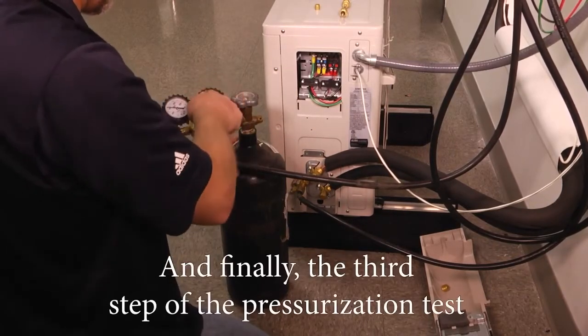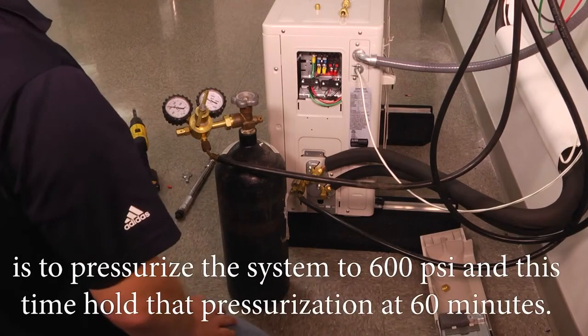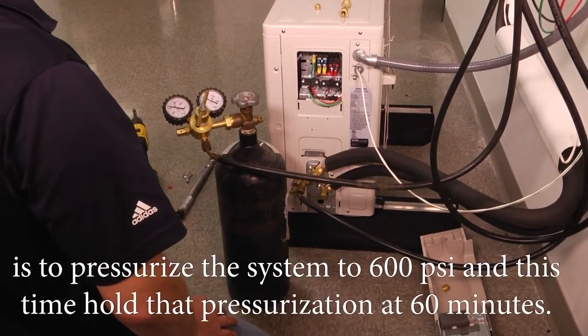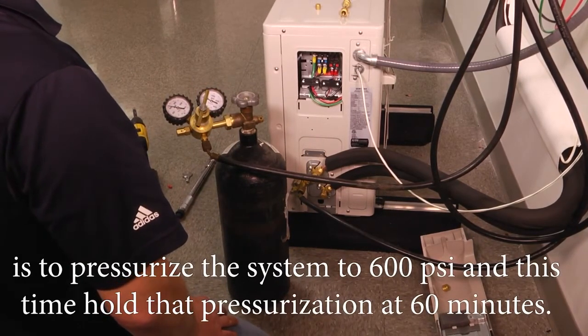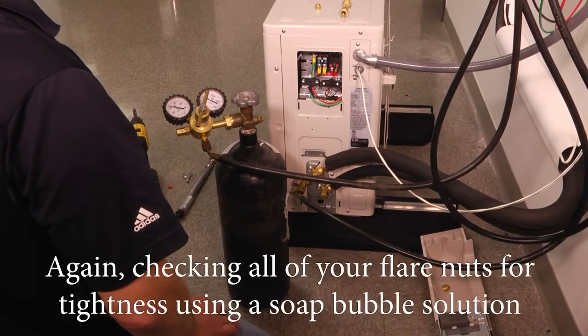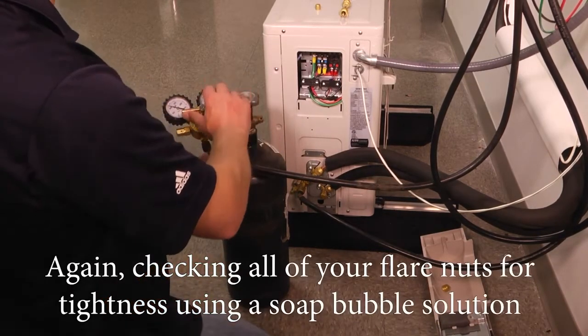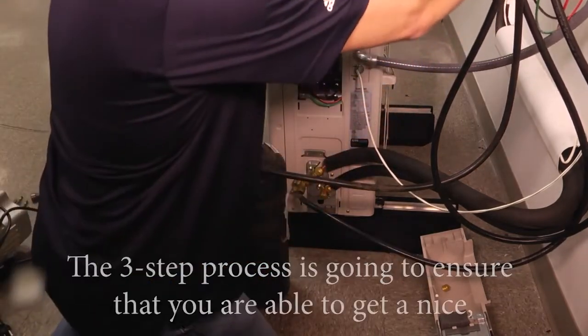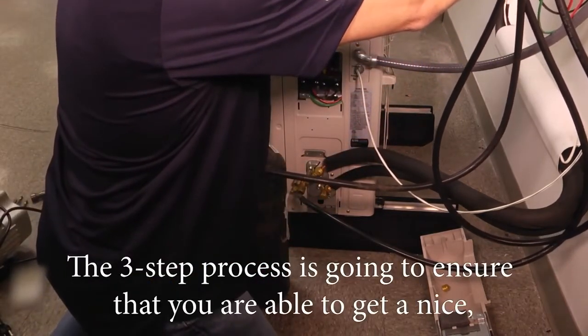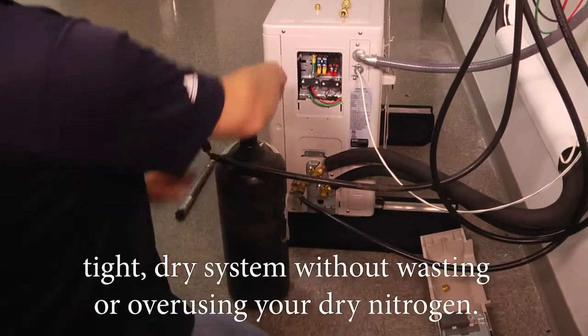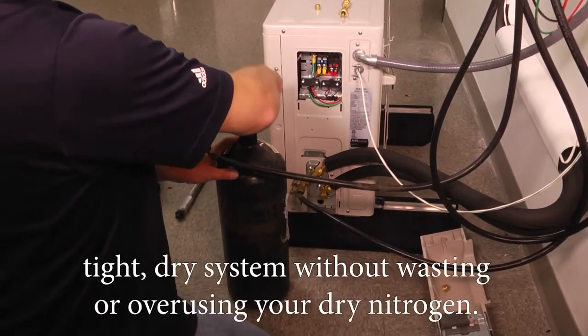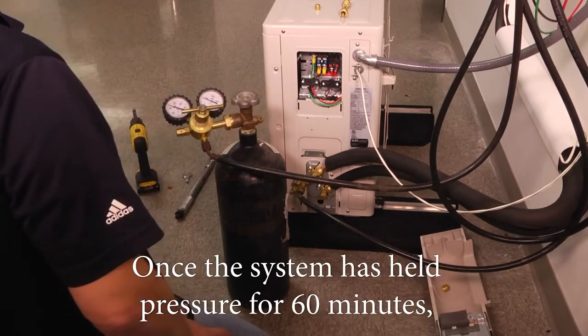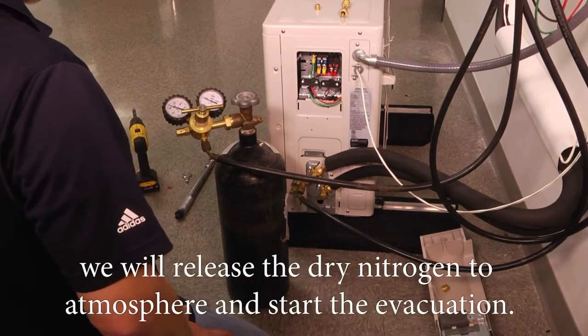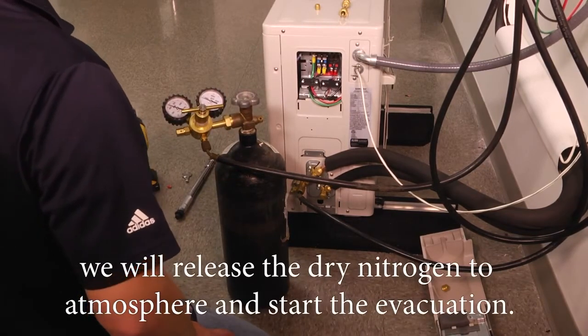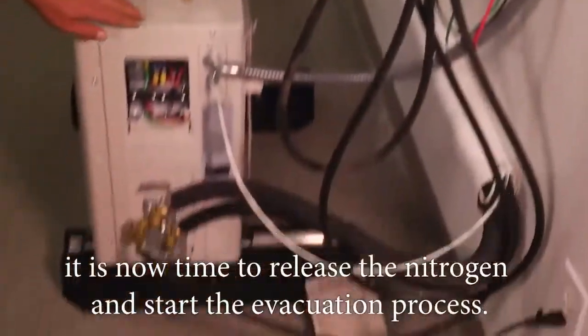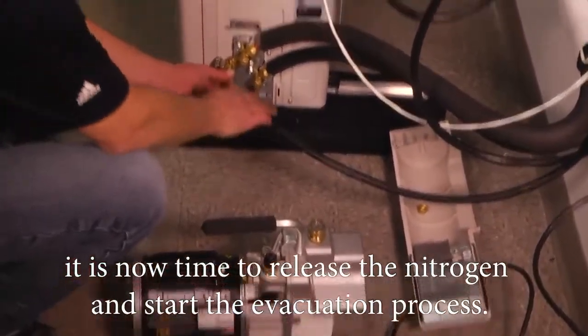And finally, the third step of the pressurization test is to pressurize the system to 600 psi, and this time hold that pressurization at 60 minutes. Again, checking all your flare nuts for tightness, using a soap bubble solution looking for any leaks that might occur. Now, this 3-step process is going to ensure that you're able to get a nice, tight, dry system without wasting or overusing your dry nitrogen. Once the system has held pressure for 60 minutes, we will release the dry nitrogen to atmosphere and start the evacuation. It's now time to release the nitrogen and start the evacuation process.